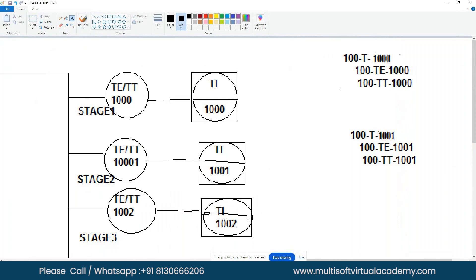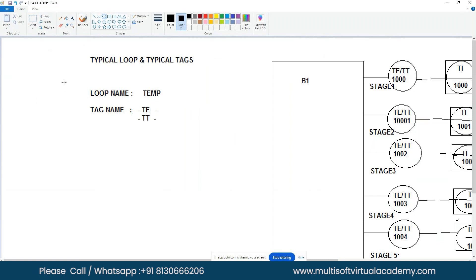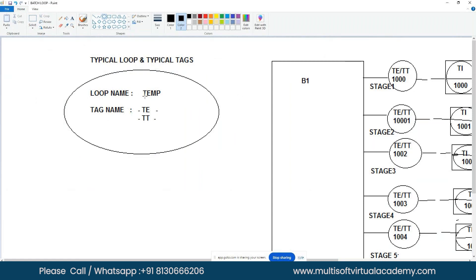When you have a similar type of loop and tags, use the batch loop and batch tag creation feature to create bulk tags — similar to making multiple copies from one page on a copy machine. First, create a typical loop with a dummy loop name and dummy tag numbers, then convert that typical loop into N numbers of actual loops.